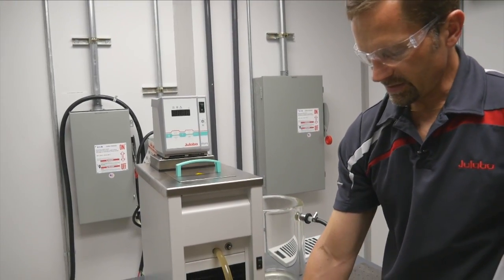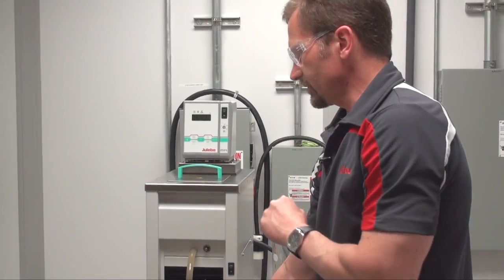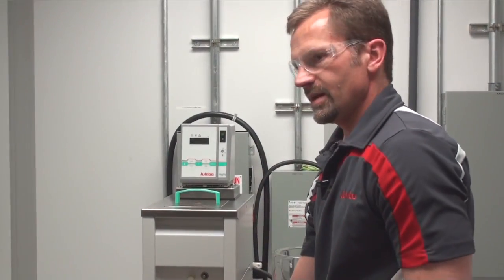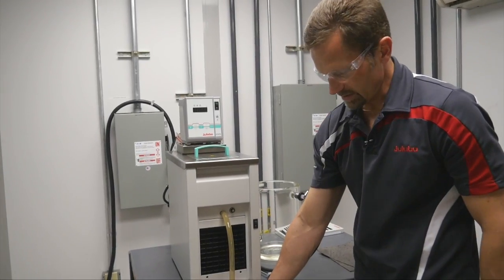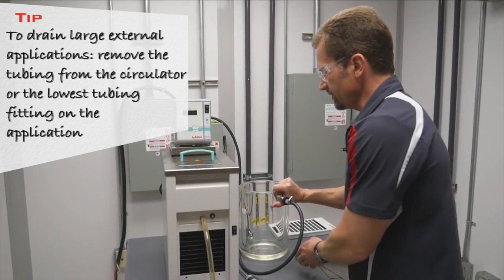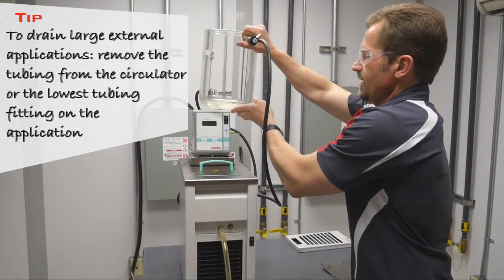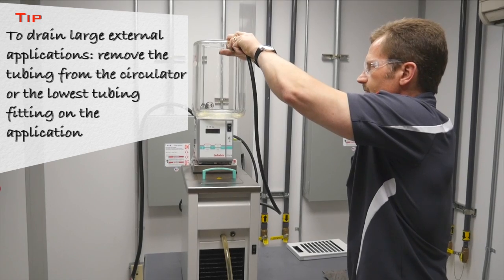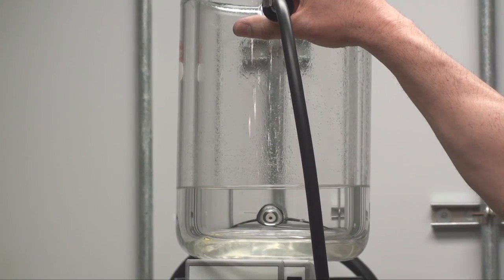Once the bath tank of the Julabo system has been emptied, if you have an external application connected to it, you could either raise the external application above the level of the circulator or remove the tubing on the back of the system to drain your external application. In this case we have a relatively small external application, so I'm simply going to lift it above the circulator and introduce some air. The fluid will drain back into the bath tank and then out into your container.